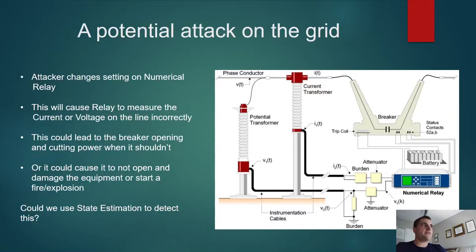Essentially for the purposes of this, we're worried about an attacker who's very subtly trying to change the setting in either the potential transformer or the current transformer, which would give a bad voltage or current reading. This could be bad because it could cause a relay to not break when the voltage conditions are dangerous, or it could cause it to break and cause disruptions when situations are not dangerous, neither of which is ideal. We're going to see if we can use state estimation to detect this in a simple example.